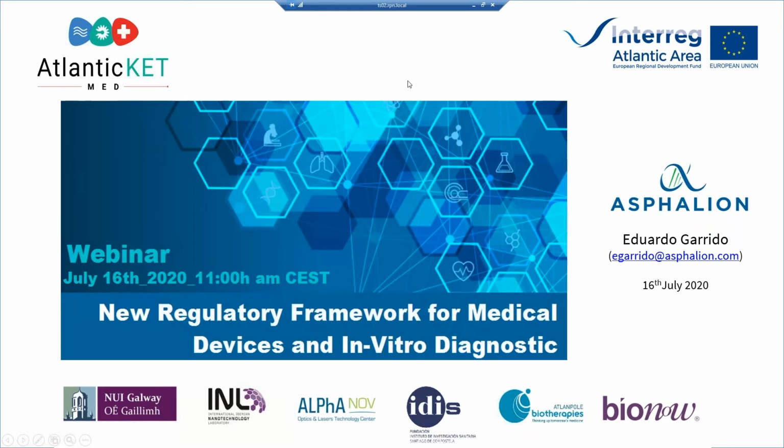So what is the certification process for a software with a single class 2A feature and all other class 1? Well, as I said before, if there are several rules applicable to your device, you've got to take the one that is higher. So you'd go to the class 2A. That always depends, and it happens a lot with software. It depends on the claims you put to your device.